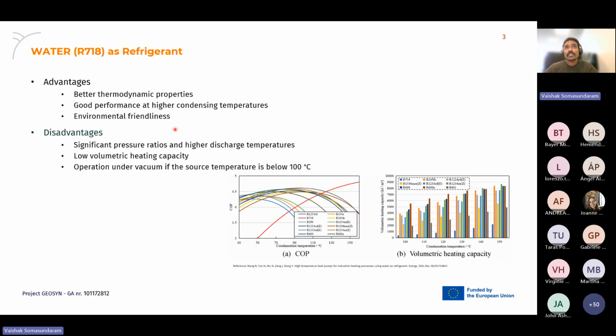However, these advantages of water come with some limitations or challenges. Water exhibits high pressure ratios as well as high discharge temperatures. In addition, it has low volumetric heating capacity, which means the compressors used for this application are bulky, as are other components. Also, if the heat source temperature is less than 100 degrees centigrade, the evaporator of the heat pump will operate in vacuum, causing additional challenges for the heat pump.